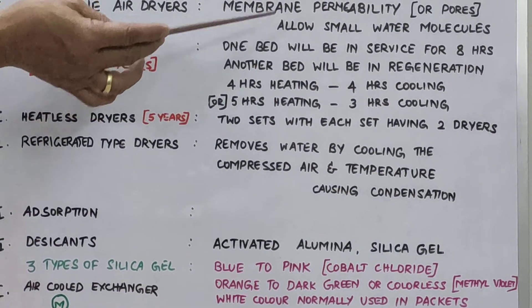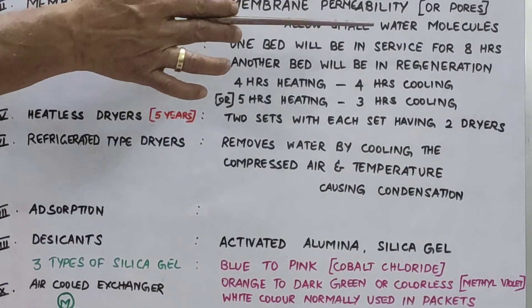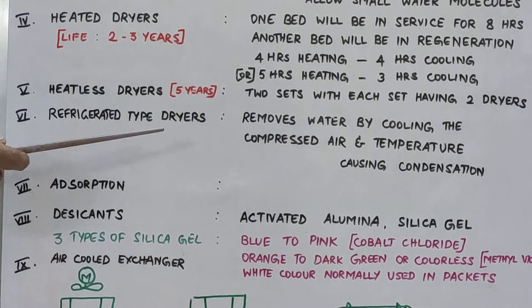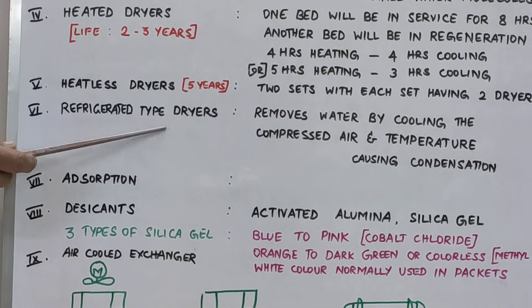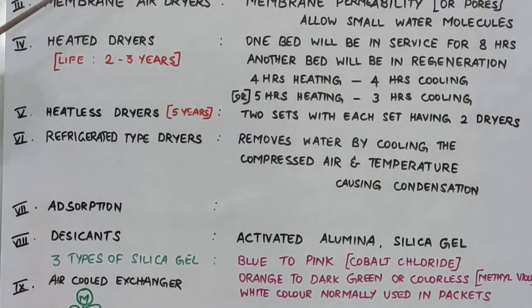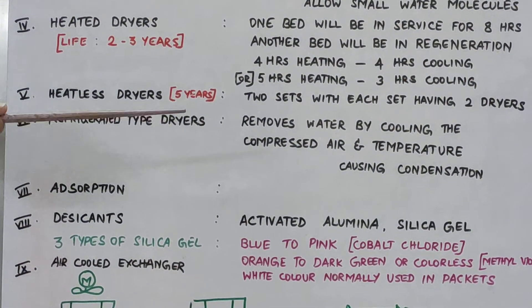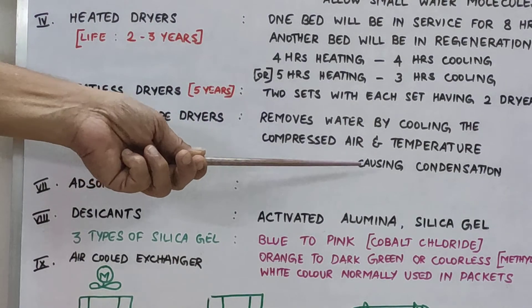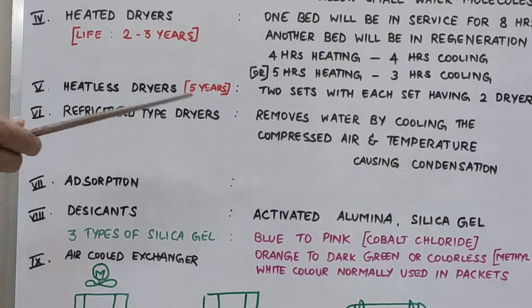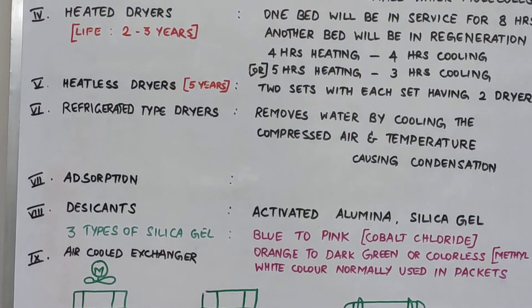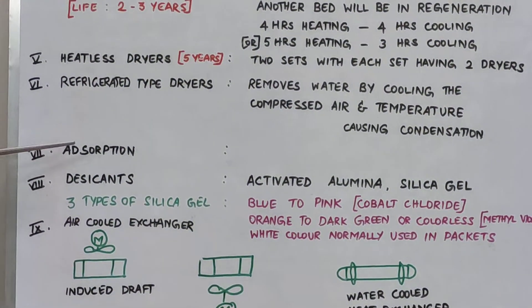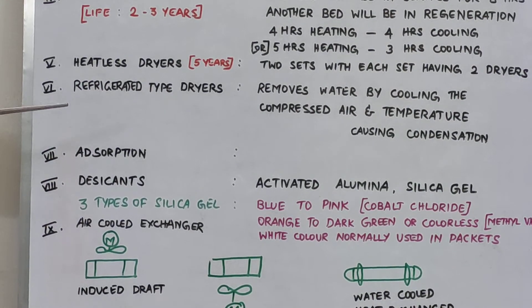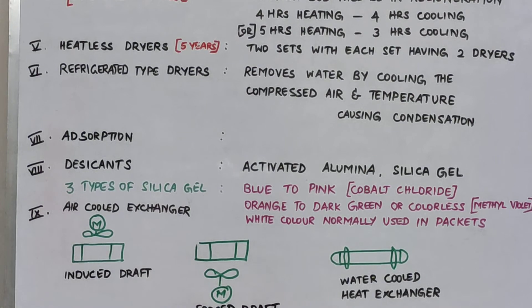Normally 10 to 20% of the dry air is used for purging, so 80% of dry air goes to the instrument air receiver. Another type is the refrigerated dryer, which is economical but slightly lower in purity compared to desiccant or membrane types. It removes water by cooling the compressed air using refrigerated coolers, causing condensation. The condensed moisture is then removed by a moisture separator. The phenomenon used in desiccant dryers is called adsorption, which is a physical and reversible phenomenon used to remove moisture.